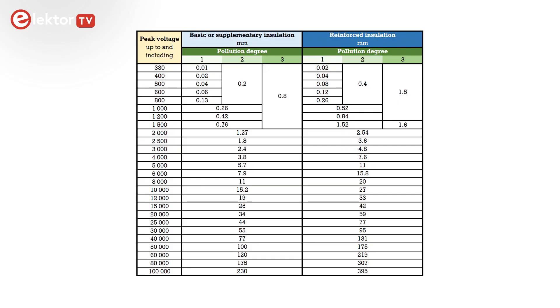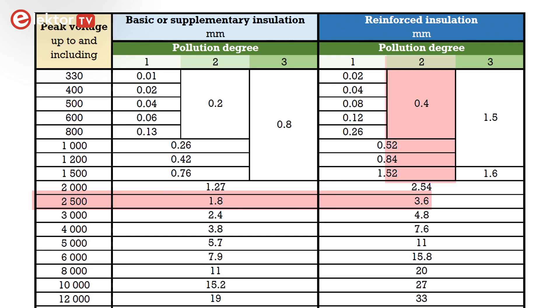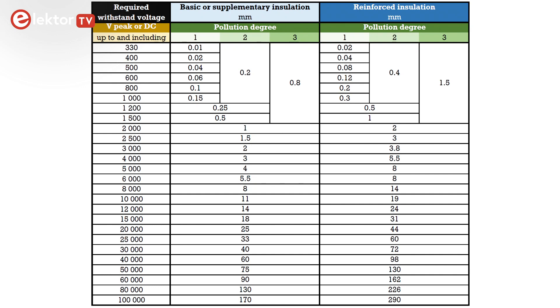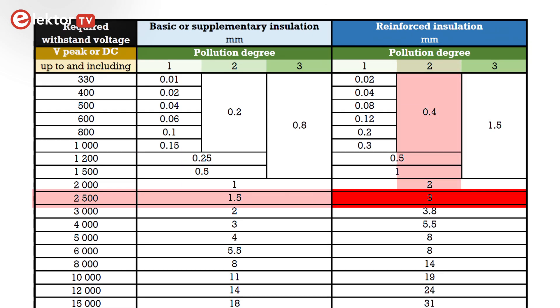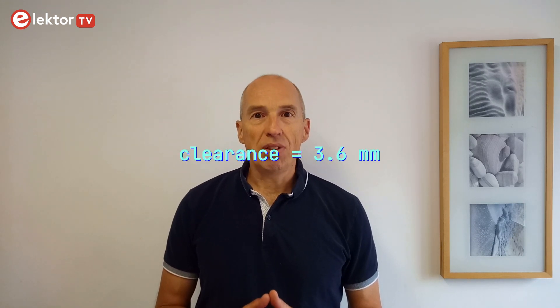To determine the clearance distance between the primary and secondary circuits there are two procedures, and you must take the highest value of the two. Procedure 1 uses Table 10 in my draft document and we find 3.6 mm for our values. Procedure 2 uses Table 14 and there we find 3 mm. Why the two values are different is unclear to me, but we must use the highest value of the two, so we continue with 3.6 mm.